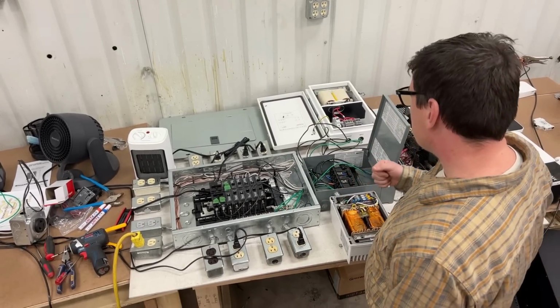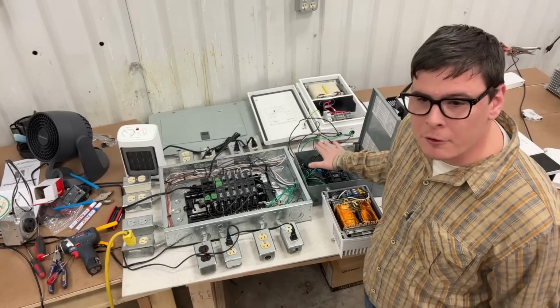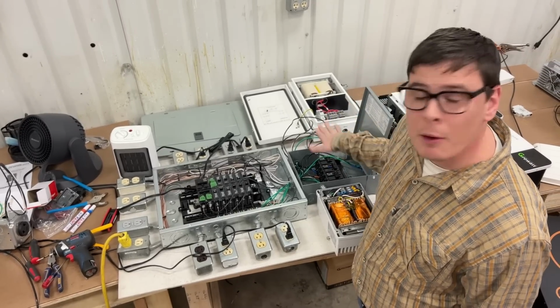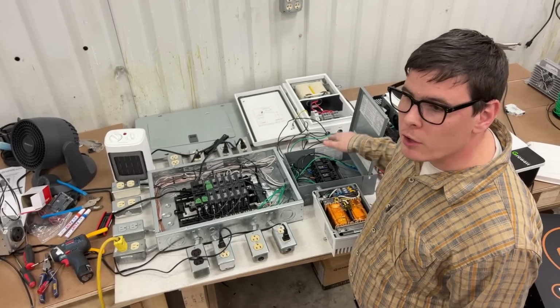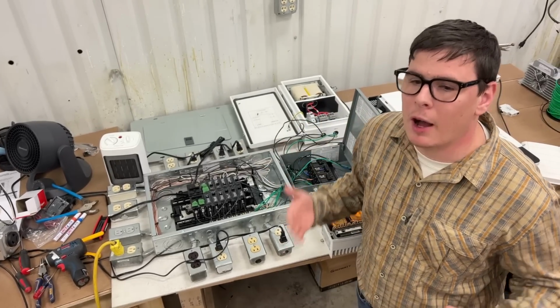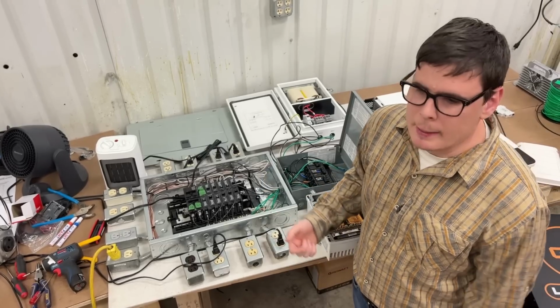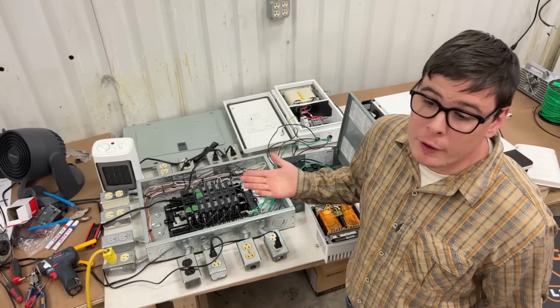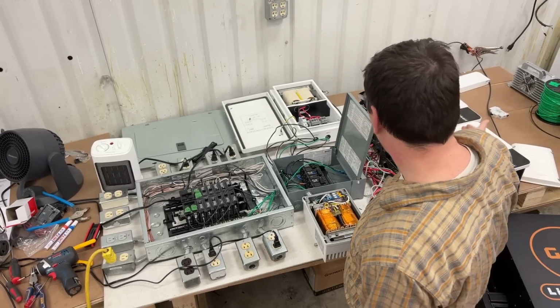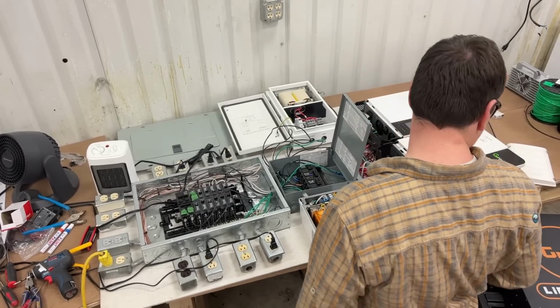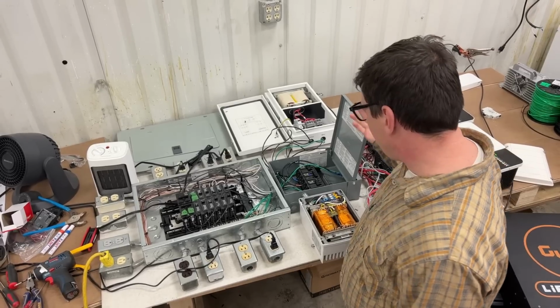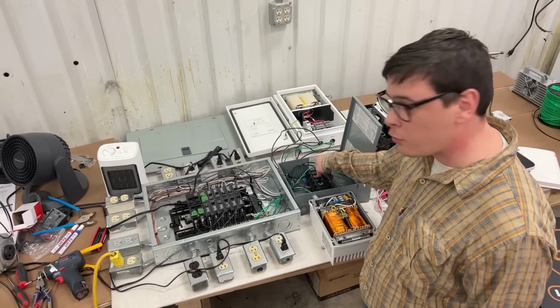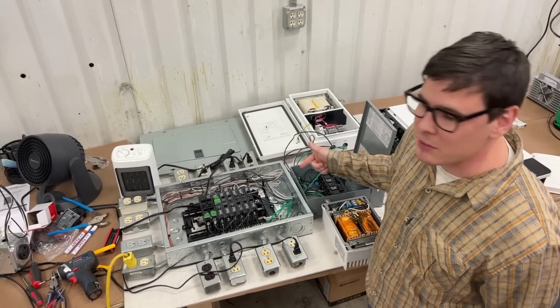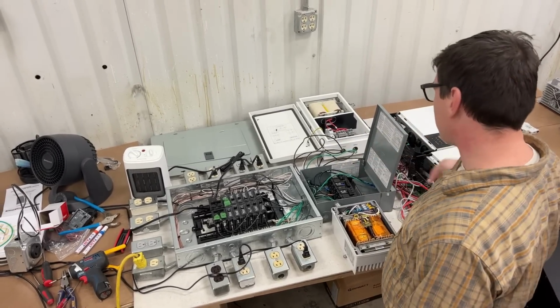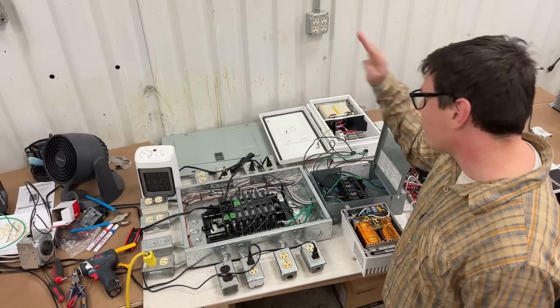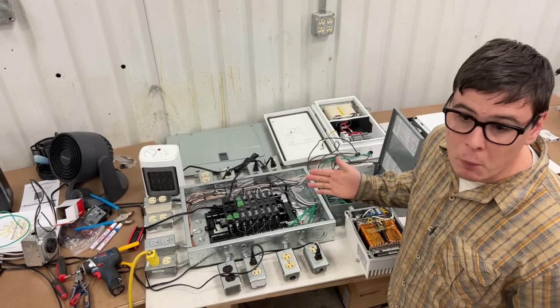But yeah, if you were an off-gridder that wanted to have 5 electric 120-volt heaters, here's how you could protect that. You would put all of your inverters together and transformers on a separate breaker panel. Okay, so that is basically your combiner box for all those inverters, you're picking up one transformer or 2 transformers. We're going to show you one transformer here. I've got one inverter running off this battery bank, and we have the transformer tied into this breaker panel.